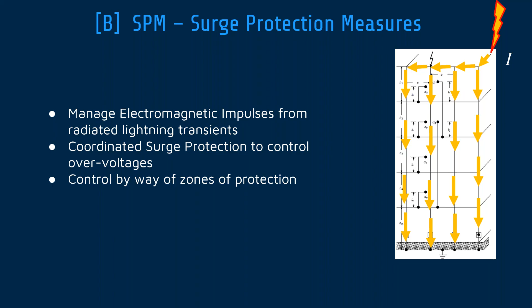So just talking about those standards, SANS 62305 is the adopted standard from the IEC. 62305-1 is general principles, 2 is risk management, 3 is physical damage to structures and life hazards, and 4 is electrical and electronic systems within structures. Now 10313 was set up as a supplementary document to part 3 of 62305 in order to advance things that are unique to South Africa. Unfortunately, we've lost the plot a bit, so I will talk you through where we are with the standards now, just looking at the time.